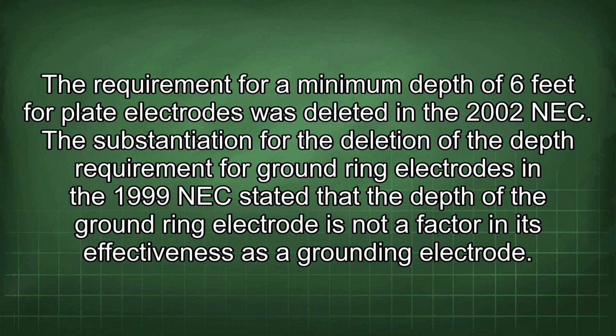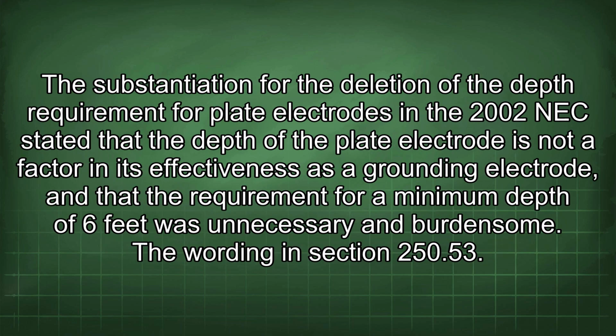The substantiation for the deletion of the depth requirement for ground ring electrodes in the 1999 NEC stated that the depth of the ground ring electrode is not a factor in its effectiveness as a grounding electrode. The substantiation for the deletion of the depth requirement for plate electrodes in the 2002 NEC stated that the depth of the plate electrode is not a factor in its effectiveness as a grounding electrode, and that the requirement for a minimum depth of 6 feet was unnecessary and burdensome.